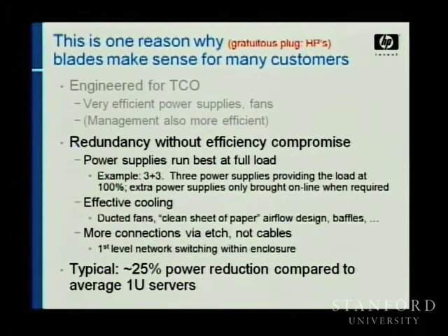The other thing that people do in blades is that they've got very nice fan designs, and there's sort of a clean sheet of paper. You're no longer in this 1U space. By the way, 1U servers are kind of interesting because the herd all loves 1U servers, but those tiny little fans are pretty inefficient. All right, so kind of open your mind a little bit. Don't think everything has to be in 1U. And just from this, a year and a half ago, we figured out that all the stuff that we did in blades typically saved us 25% of the power bill compared to a 1U server.